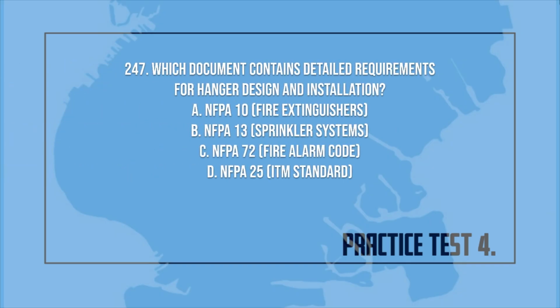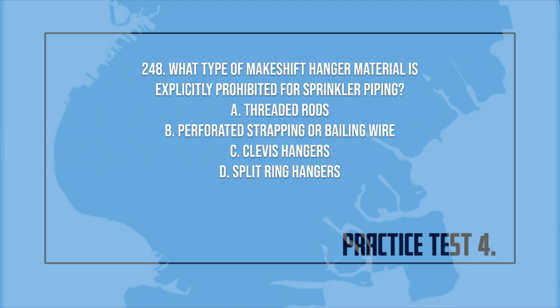247. Which document contains detailed requirements for hanger design and installation? A. National Fire Protection Association 10, Fire Extinguishers. B. National Fire Protection Association 13, Sprinkler Systems. C. National Fire Protection Association 72, Fire Alarm Code. D. National Fire Protection Association 25, ITM Standard. 248. What type of makeshift hanger material is explicitly prohibited for sprinkler piping? A. Threaded rods. B. Perforated strapping or baling wire. C. Clevis hangers. D. Split ring hangers.